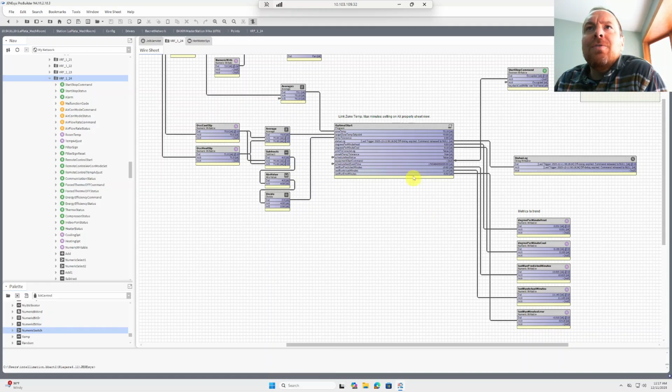So for a VRF system, a cassette where this optimal start block is running, I am getting some good performance that I can see with only a couple days of data on the quadratic model. Feel free to reach out if you want to try installing these. I'm having better luck with the built-in Tridium Optimal Start, which hopefully Tridium will update.